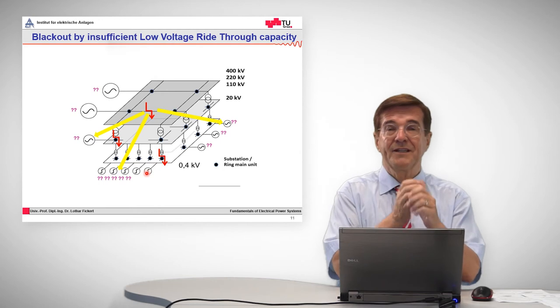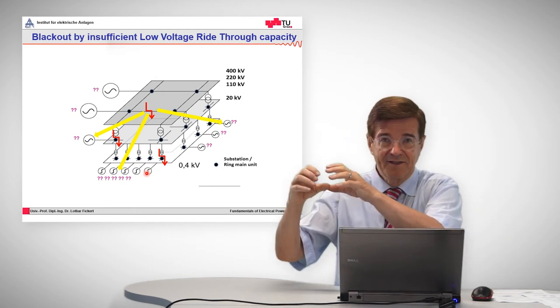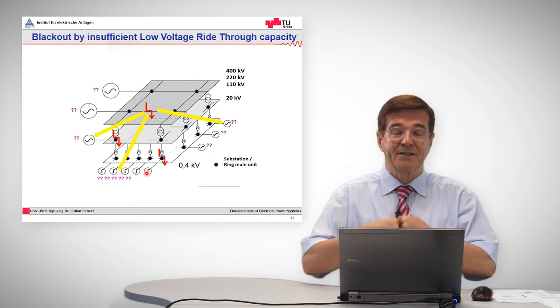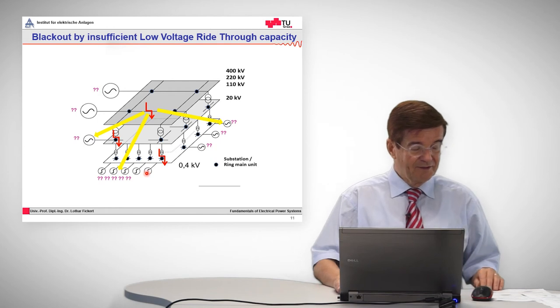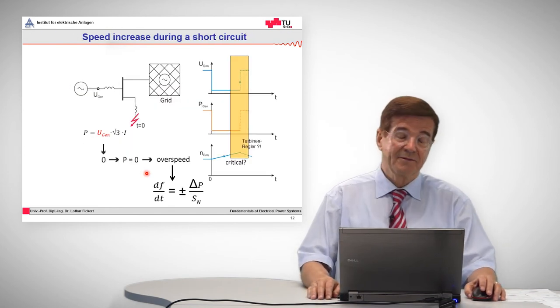And that means that all these generators that have these decentralized in-feed, they have no synchronizing voltage anymore. And that leads in many cases to the loss of stability. When there is no voltage, there is no power exchange between the generator and the system. So the system is not kept energized anymore and the generators trip out as well. So this is the low voltage ride through capability induced breakdown.